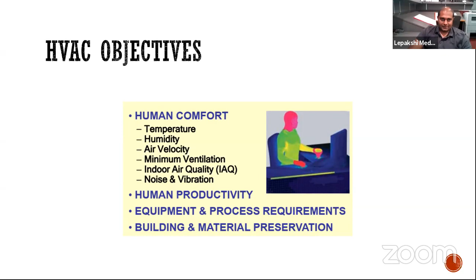Noise and vibration also matter — if you're sitting in an office or institution, you don't want noise from the ductwork; it's annoying. So you've got to pick the right materials to reduce noise, like putting in sound attenuators or duct lining such as acoustic liners inside the duct to suppress sound. These are the objectives to keep in mind while designing your system.